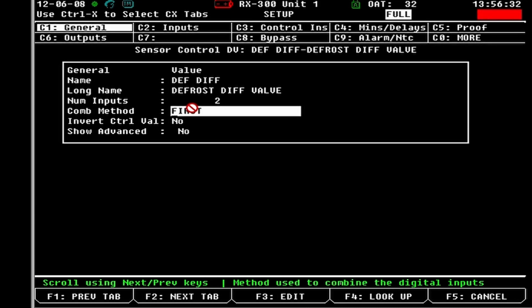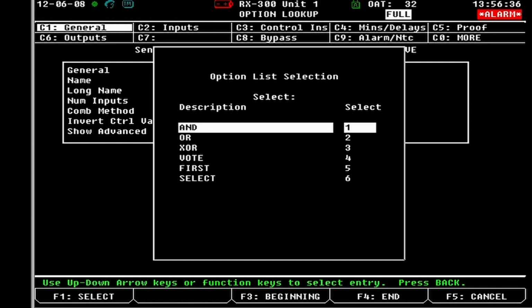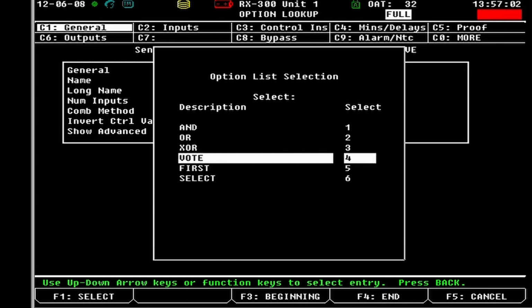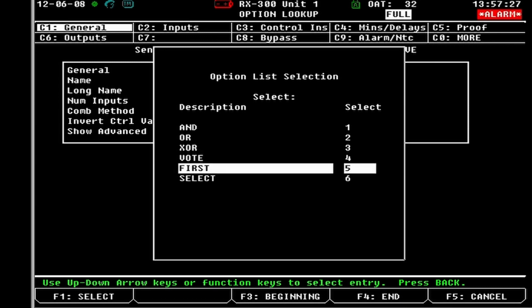And then you have combination method. So if you hit F4 lookup, you have AND, which means both have to be on. So it'd be input 1 and input 2 have to be on for it to make its closure. You have OR, which would be input 1 or input 2 has to be on for it to be on. You have XOR, so it's OR and NOR. You have vote, so we can take a vote of how many inputs are on and how many inputs are off, and whichever one has the highest number. So if you have 2 inputs on and 2 inputs off, it's going to error out. If you have 3 inputs on and 1 input off, it's going to be on. And then you have first. So whatever input is on or off first will be your deciding factor.